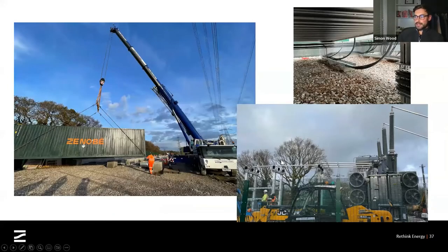A couple of images there showing some of the containers being lifted into position. At the bottom there, you can see some of the final assembly work being done on the 33 kV side of the transformer. And then you've got the main bushings and bus bars connecting onto the 275 kV side of that transformer there. Here you can see some of the DC cabling that comes down and loops across from the battery containers up into the inverters, which are next door to each other.